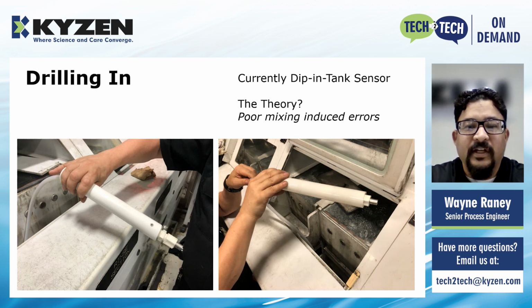This is what the sensors looked like before we changed them. These are the dip-in-tank style sensors, and we had a theory that they were not measuring a well mixed sample of the chemistry. Essentially, they were in dead areas. We plan on changing these to an inline sensor, which will measure a well mixed concentration coming directly off the wash pump and directly off of the rinse pump.